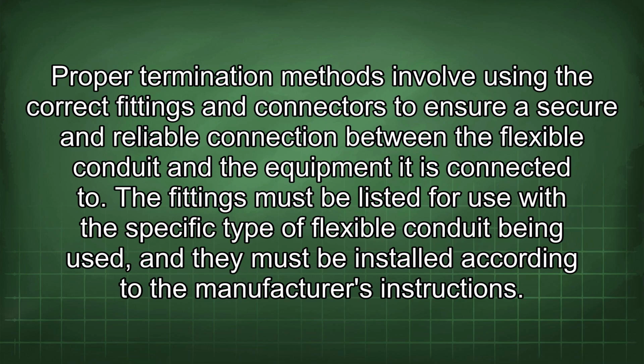Proper termination methods involve using the correct fittings and connectors to ensure a secure and reliable connection between the flexible conduit and the equipment it is connected to. The fittings must be listed for use with the specific type of flexible conduit being used, and they must be installed according to the manufacturer's instructions.